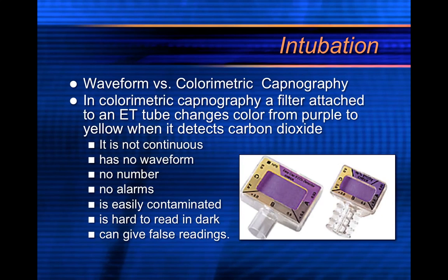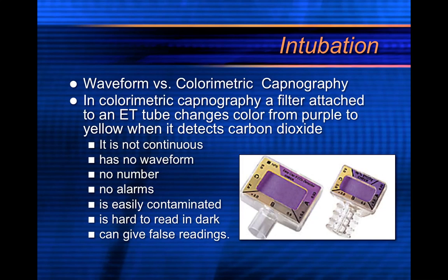Waveform versus colorimetric capnography — they are worlds apart. In colorimetric capnography, a filter attached to the ET tube changes color from purple to yellow to detect the presence of carbon dioxide. It's like litmus paper. It is not continuous, has no waveform, no number, no alarms, is easily contaminated, hard to read in the dark, and can give false readings. Those of us who've gotten waveform capnography might not even put colorimetric devices on BVMs anymore because they're almost useless.